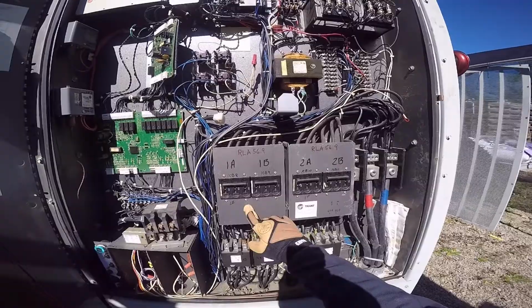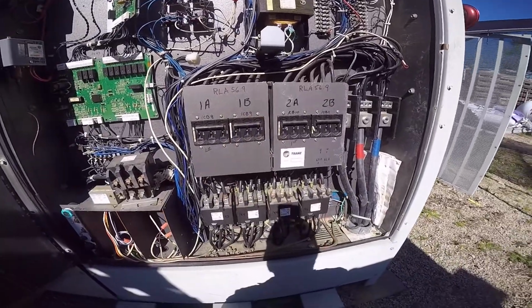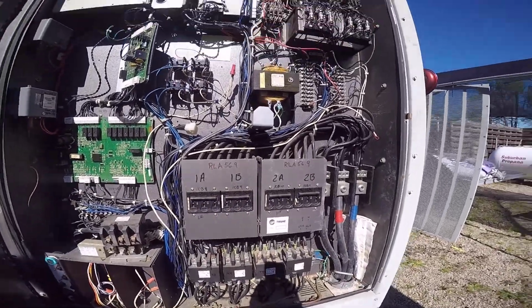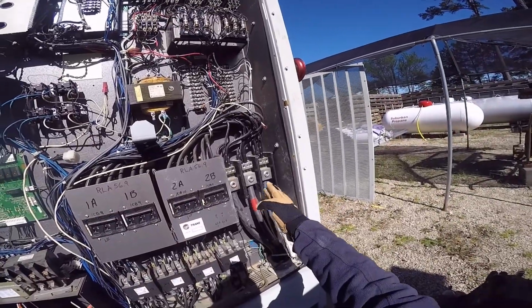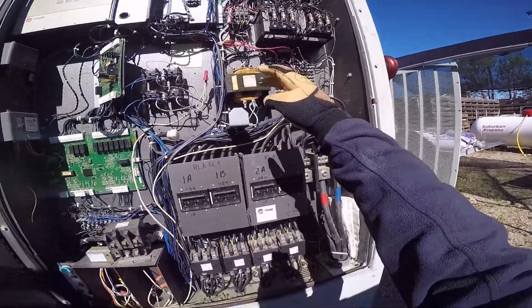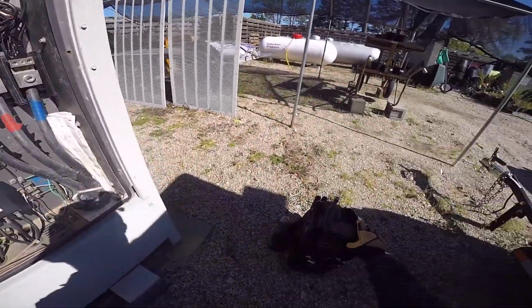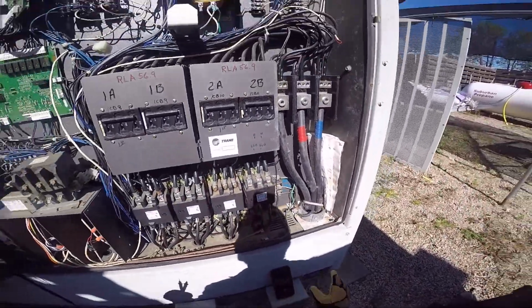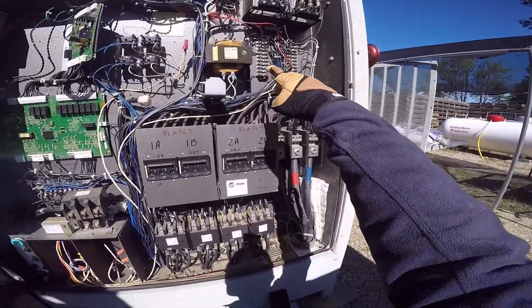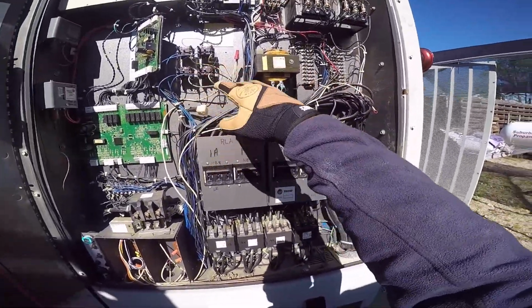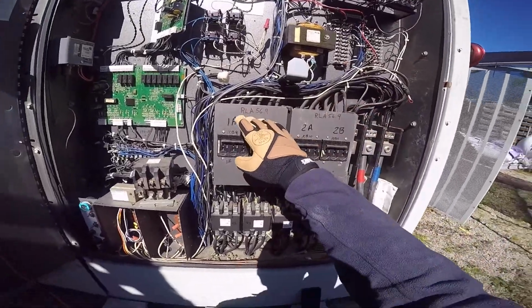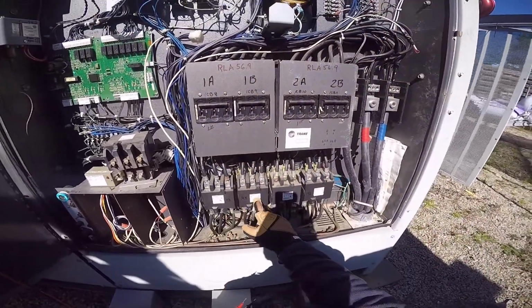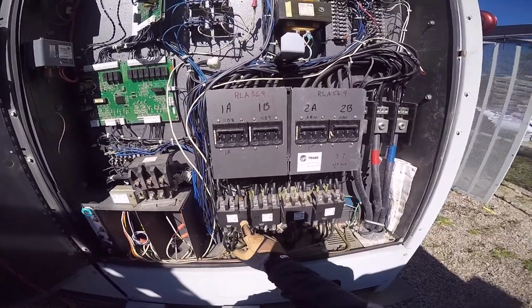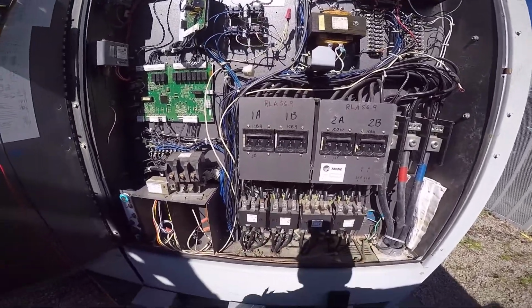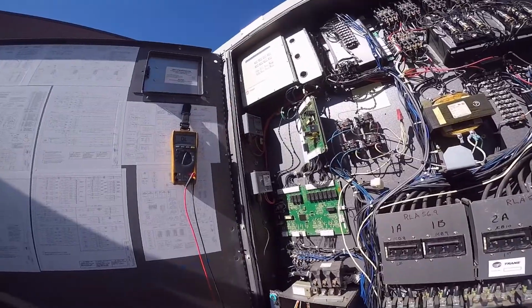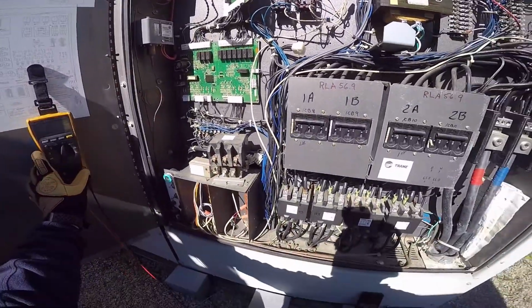Now I have overload circuit breakers for our compressors, and we come out of the service L1, L2, L3 into the top of the breakers. So out of the service into the top of the breakers, L1, L2, L3. We come out of the breakers and we come down here to the compressor contactors, which I have labeled 1K3, 5, 4, and 6. Okay. And I'm still on ohms. I'm going to slide my meter down here.